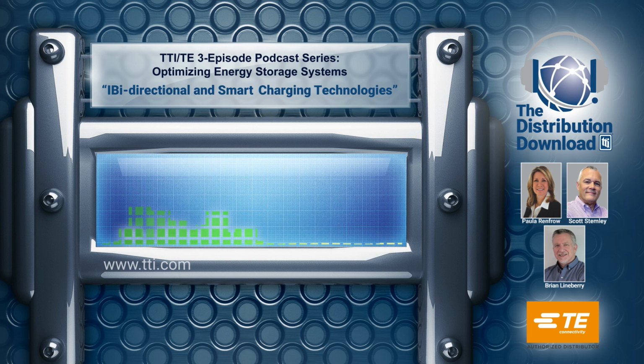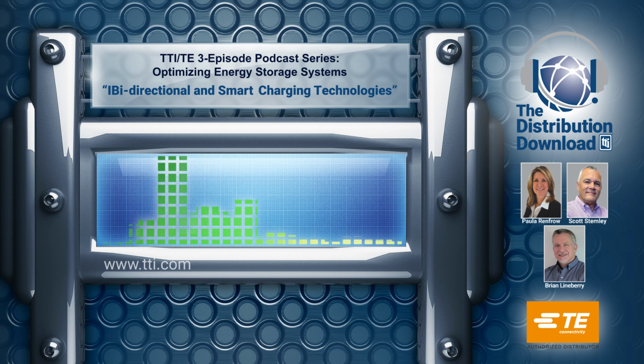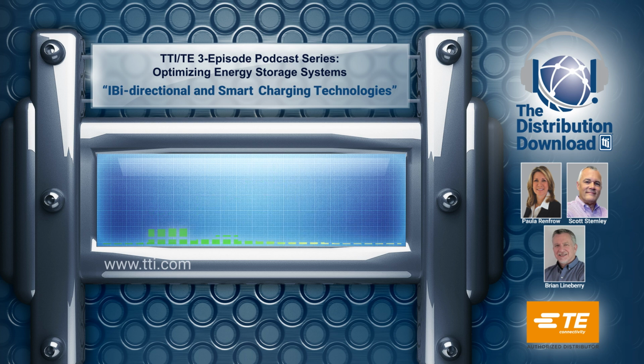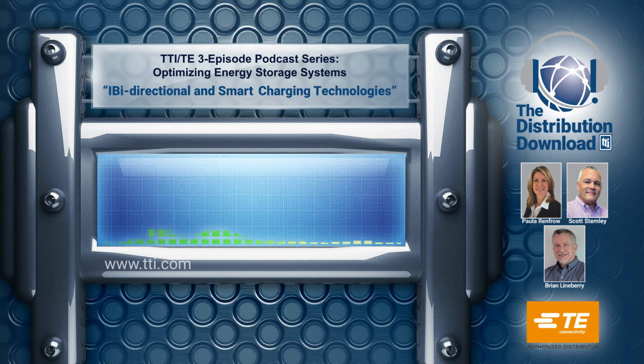How do relays and contactors improve upon the older technologies when it comes to battery storage systems? Yeah, I guess the main thing that makes these smart systems possible is the bidirectional design of the contactor. And there's a lot of components, but the contactor is our focus here. Traditionally, DC contactors would use a magnet inside the contactor. The magnet is there near where the arc is created. As a contactor opens, there's an electrical arc that is created inside. As the contactor disconnects, as we mentioned earlier, that disconnection of the circuit, that electrical arc impacts the contactor life. So we want to reduce the arc.